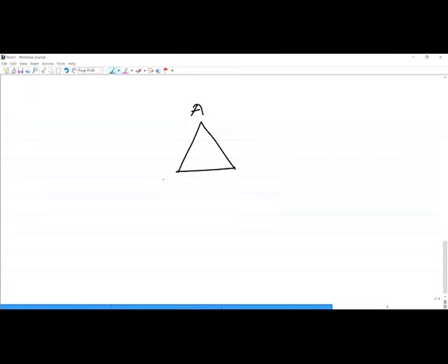Let us say these are the 3 sensors A, B and C, which are placed in these 3 locations. Okay. So, like that you should place them in a particular pattern or in a particular shape, so that you know how exactly they are placed, and as I said, what is the distance between them, so on, so that you can identify the locations of the acoustic emission source around them.